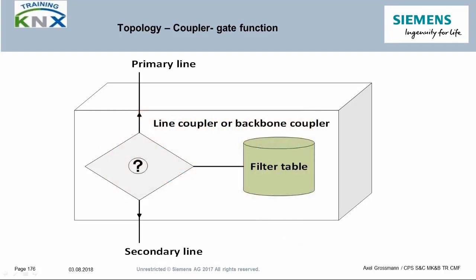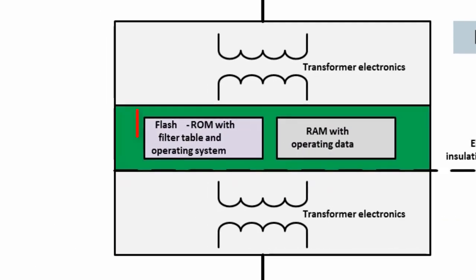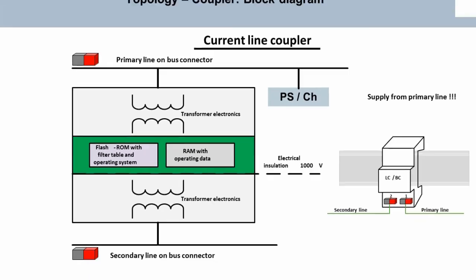Therefore, line repeaters always forward all bus telegrams unfiltered in both directions. This feature can cause problems when programming bus devices as well as during normal group telegram traffic, and should therefore only be used in special situations where the effects of the repeaters have been well investigated. The line couplers used today have a memory space in the flash ROM that holds the filter table. Since the flash ROM, like the EEPROM, is a non-volatile memory that can be overwritten frequently, this filter table is retained even when disconnected from the power supply.